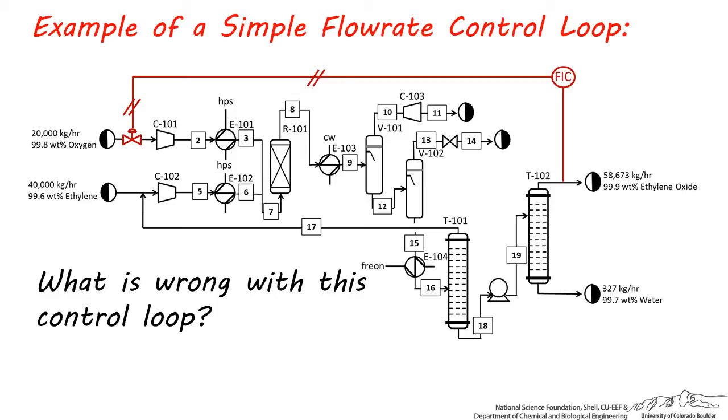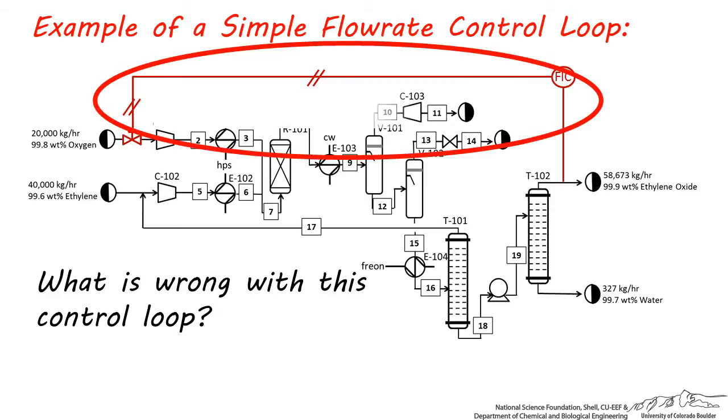One of the main issues here is that it most likely takes 30 to 120 minutes or more for a component to enter the process at the very beginning and make its way all the way through to the exit. This means that if flow rate at the exit is too low or high, the signal is already 30 to 120 minutes too late. This control loop's dead time is just too large.